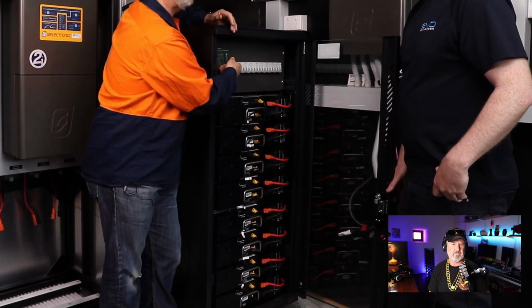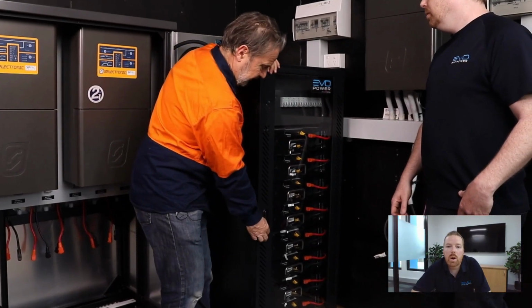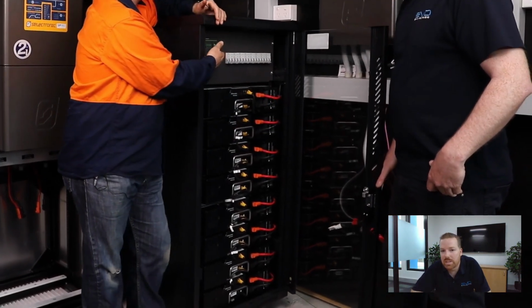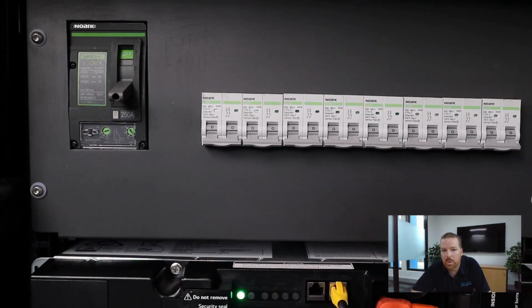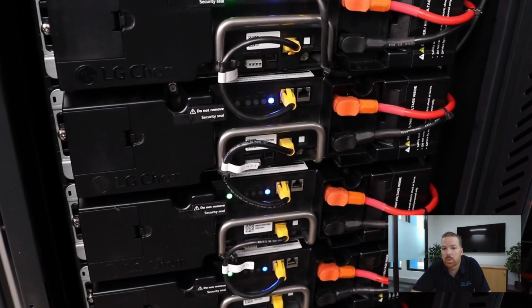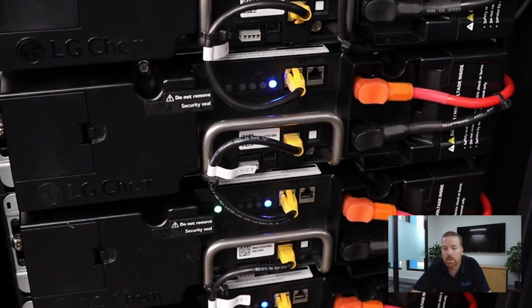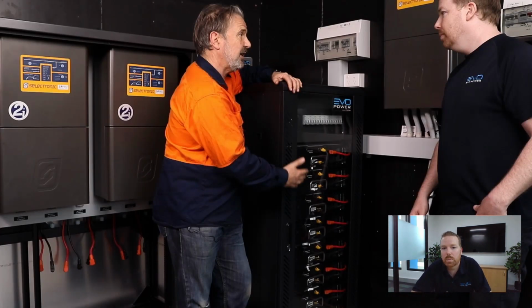Yes, so obviously we've got the main unit, which is an outdoor enclosure, but we've also developed an indoor rack style solution, we call this the M48 Select. It's paired up with exactly the same battery modules. We've got all the DC protection within there, breakers to the inverter isolator, and all the individual DC breakers. We pre-wire all the DC Amphenol connectors and all the comms is ready to go. We also pre-wire the DC cable coming from the battery rack to the SELECTRONIC inverter, so we basically have this as a package solution. We provide the inverter, the batteries, the rack, everything together as another plug-and-play solution.